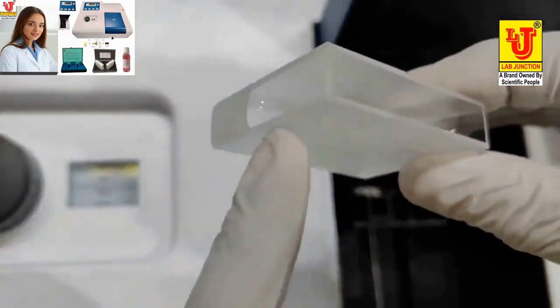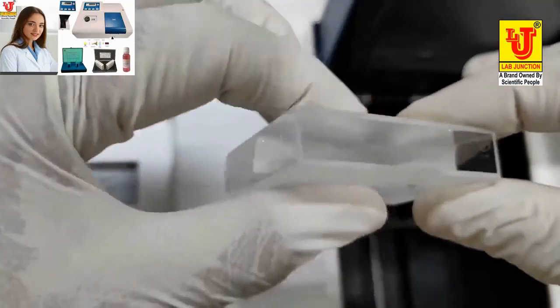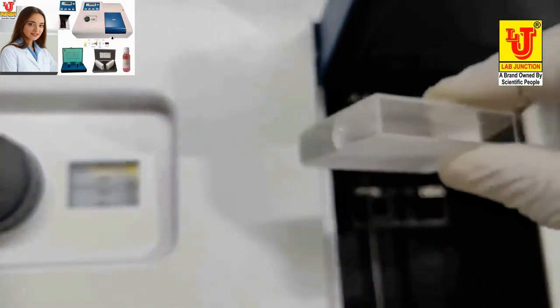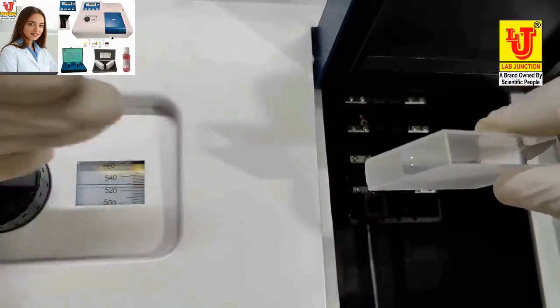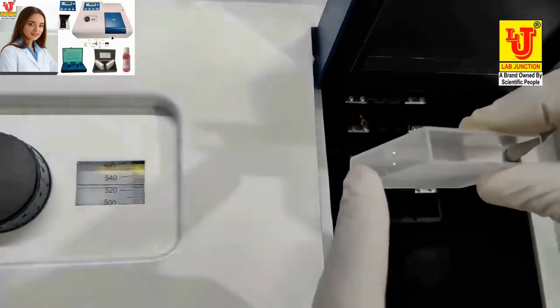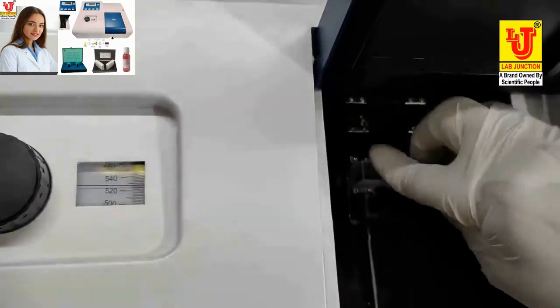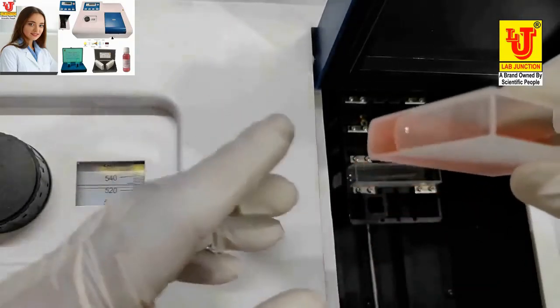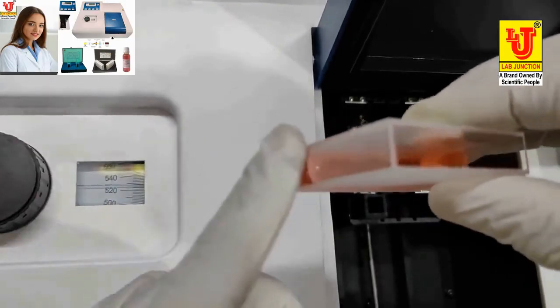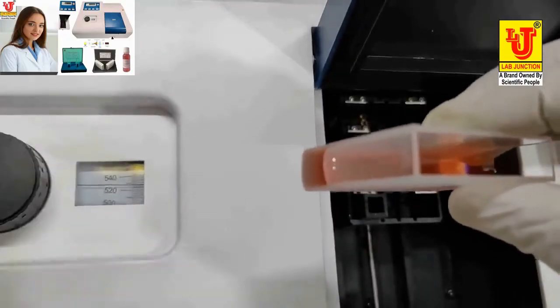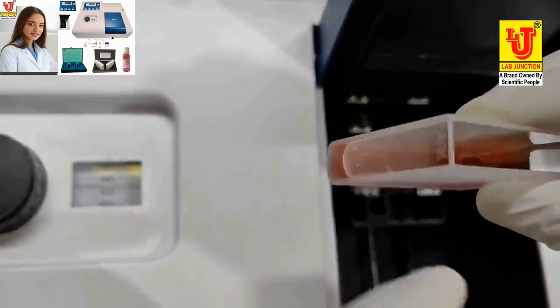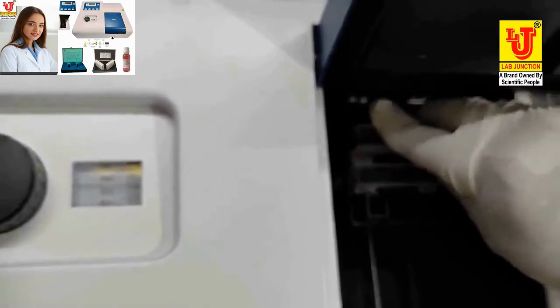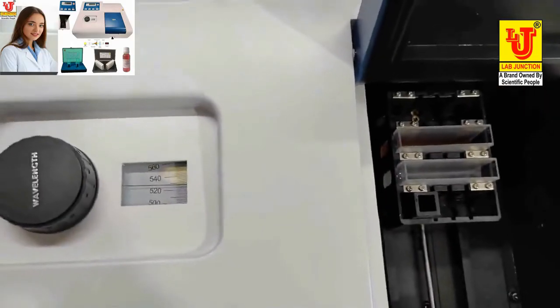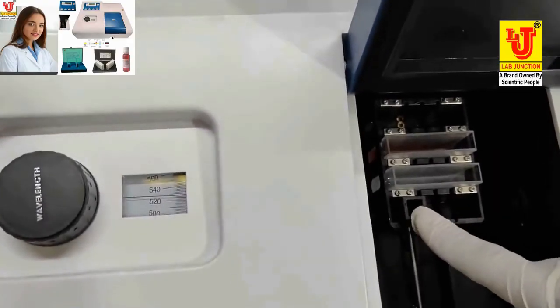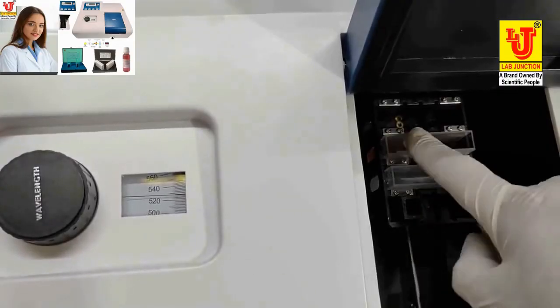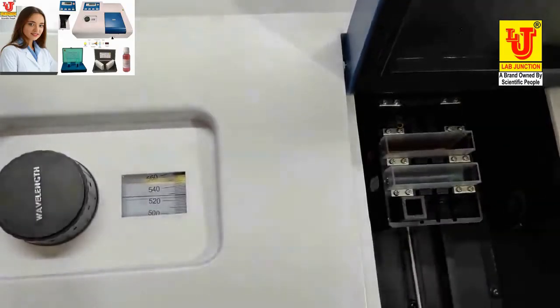50 mm path length cuvette. These two are visible sides. These sides are opaque. Now the spectrophotometer beam goes this way, so always keep the visible side in this way. This is the sample. Visible, opaque. See clearly. First is on dummy, blank, sample. You can also, one sample is there.